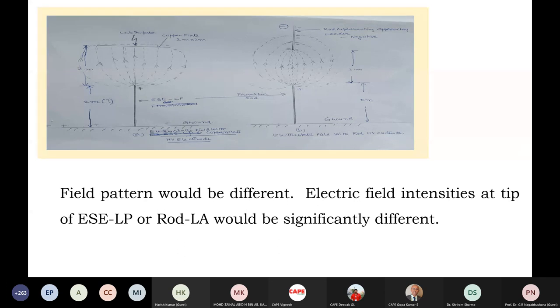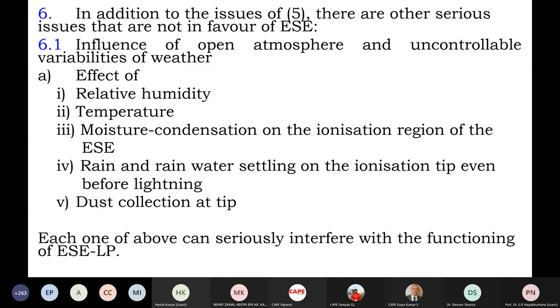If you take an actual plot or make a computer simulation, it can be found that the electric field density at the tip of the ESE or the Franklin rod will be very much different and may be much, much stronger in case of both the rods. Therefore, what will be the impact of this rod geometry, the electrode geometry, on the flashover characteristics? Will it still permit 10 microseconds deviation? And 10 microseconds at what voltage level, as I already mentioned? So going further, there are other serious issues that are not in favor of ESE.